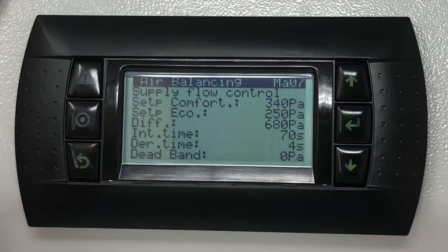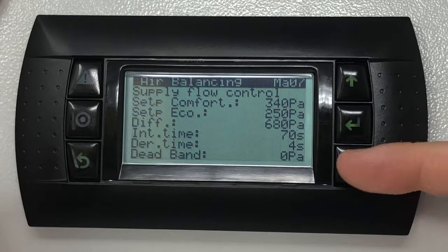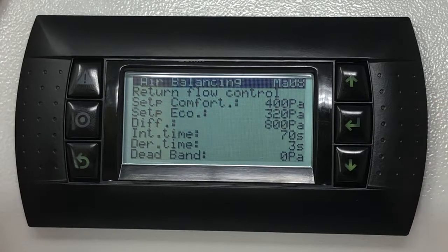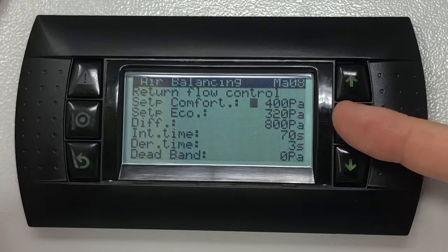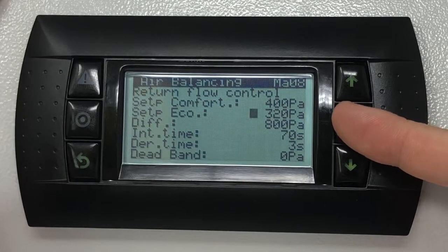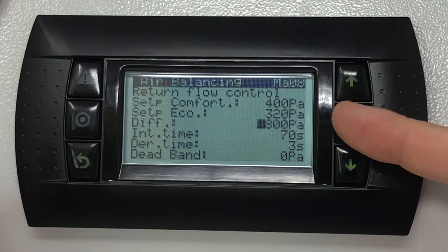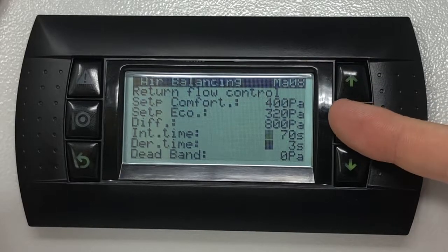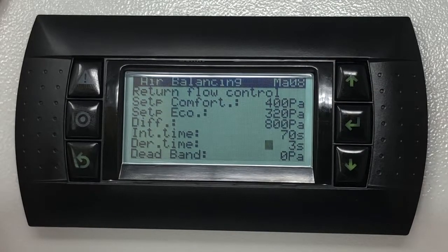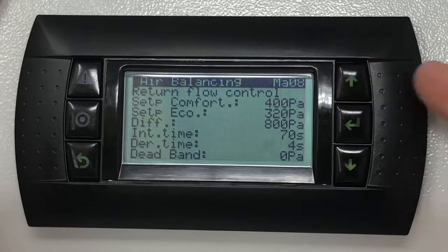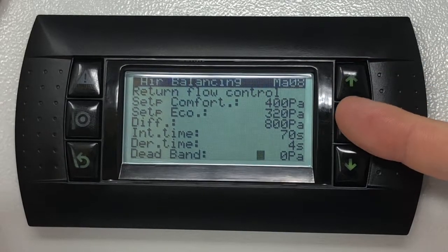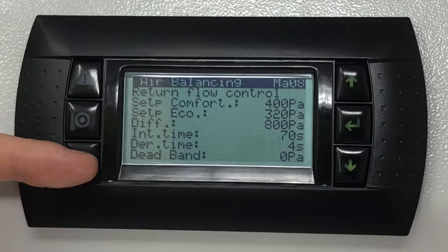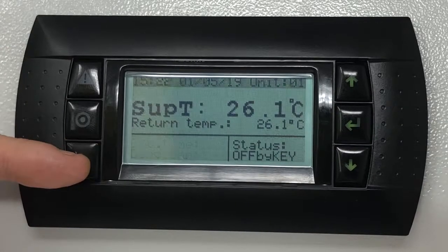Once you've set the desired settings, press the down key to view the return fan pressure control settings. These will be visible on screen MA08. Adjust the settings for the return fan pressure control as required. Once complete, press the escape button to return to the home screen.